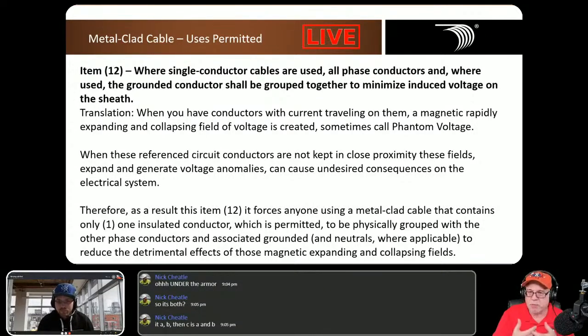But they have to be run in close proximity because we have what's called expanding and contracting magnetic fields that can induce voltage onto any metal that might be near it, in this case, the armor. And it can create all kinds of problems in a system. And we know what phantom voltage costs all of us, the headaches when you're out there testing systems. Same kind of concept, but basically this is requiring you to run all the phase conductors and any of the grounded conductors all together. And this is what this is saying.